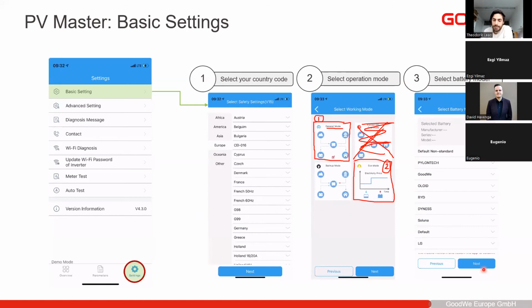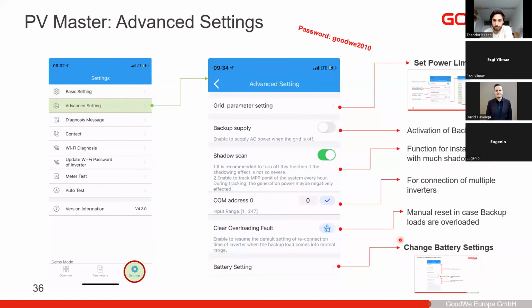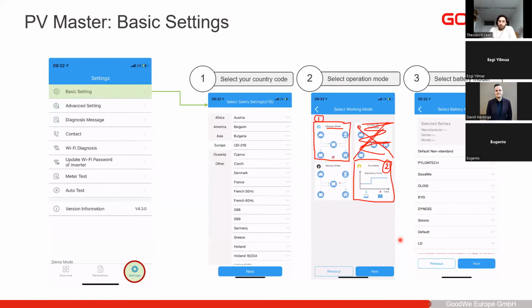If you press next, it will also take you to a slide showing a meter test. This is a test you can only do if you have a battery connected, and it will help you check if you've done the installation correctly, so basically to check if you installed the CTs and the meter correctly. I recommend running this if you have a battery installed; otherwise, you can just skip it and do it at a later stage. When you're done, the inverter will say everything is fine, and it will restart with all the new settings applied.